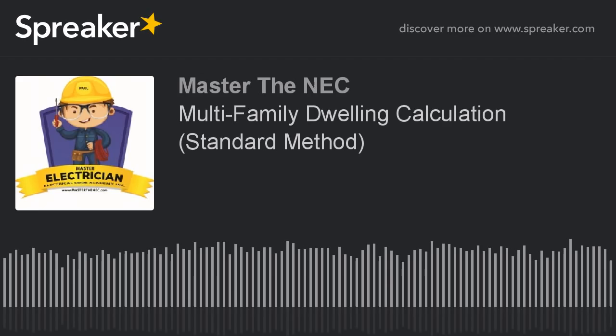The reason I'm telling you the 120/240 volts is because we are going to calculate neutral conductor sizes, or the load that's going to be on the neutral conductor. So you need to take that into consideration. And lastly, every unit that has air conditioning or heat has an air handler. The motor in this air handler is our largest motor, a 0.5 horsepower air handler at 120 volts. So that is the largest motor. I want to throw that out there.